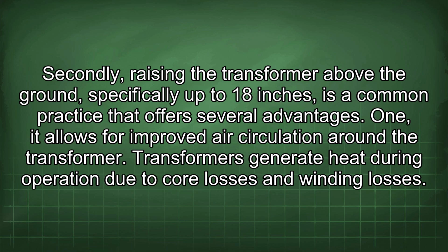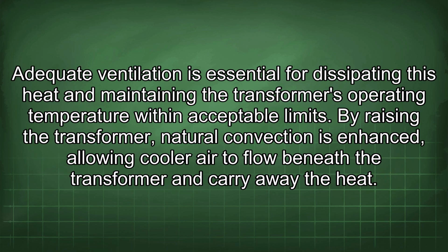Secondly, raising the transformer above the ground, specifically up to 18 inches, is a common practice that offers several advantages. 1. It allows for improved air circulation around the transformer. Transformers generate heat during operation due to core losses and winding losses. Adequate ventilation is essential for dissipating this heat and maintaining the transformer's operating temperature within acceptable limits.